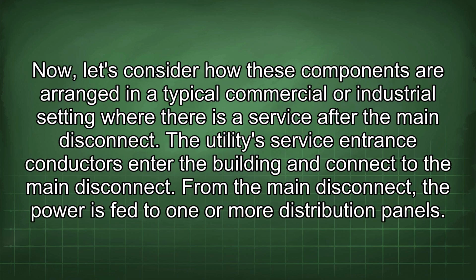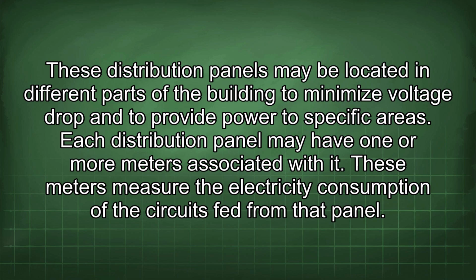Now let's consider how these components are arranged in a typical commercial or industrial setting where there is a service after the main disconnect. The utility's service entrance conductors enter the building and connect to the main disconnect. From the main disconnect, the power is fed to one or more distribution panels. These distribution panels may be located in different parts of the building to minimize voltage drop and to provide power to specific areas. Each distribution panel may have one or more meters associated with it. These meters measure the electricity consumption of the circuits fed from that panel.